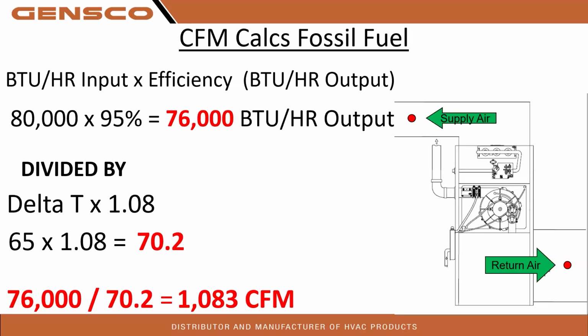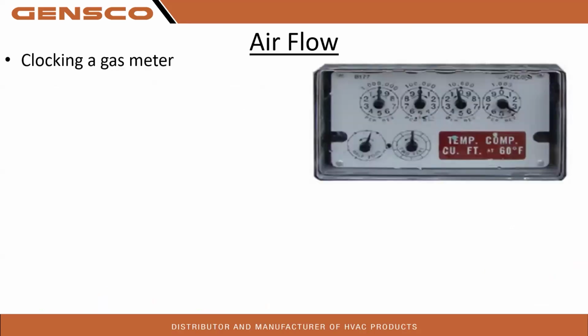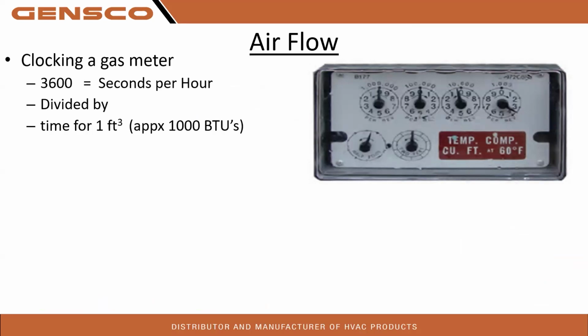So when that filter starts getting plugged, we can actually see that static pressure increase. We can see the static pressure decrease when that filter is changed. So no more of those homeowners telling us, yeah, I change my filter every 4 months. Well, we can actually see it in the data when they change the filter. Okay, here's that airflow, clocking a gas meter. I've only had to do this a couple times, but it is a good method.